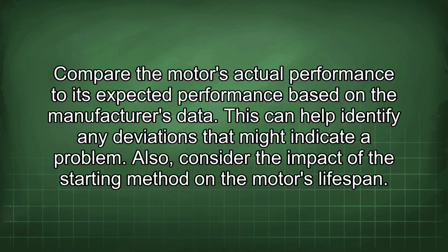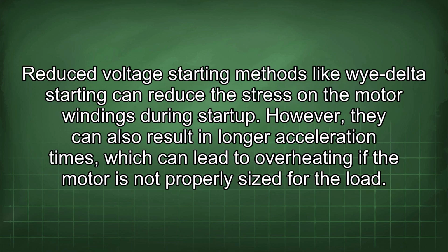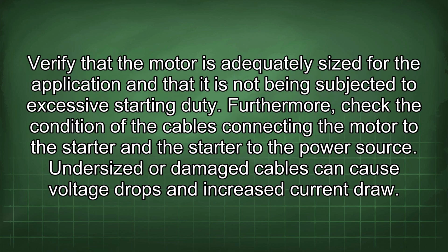Also, consider the impact of the starting method on the motor's lifespan. Reduced voltage starting methods like Wye-Delta starting can reduce the stress on the motor windings during startup. However, they can also result in longer acceleration times, which can lead to overheating if the motor is not properly sized for the load. Verify that the motor is adequately sized for the application and that it is not being subjected to excessive starting duty.